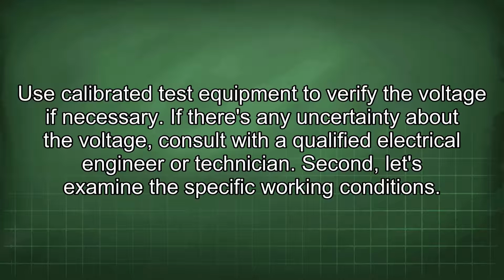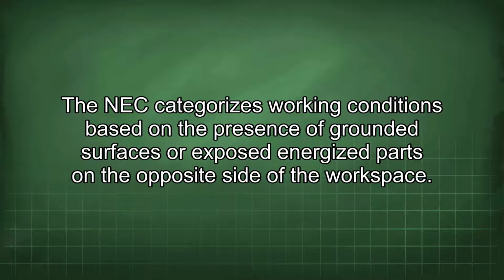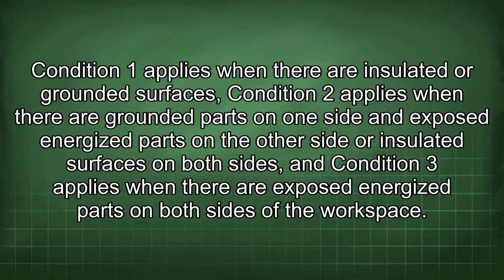Second, let's examine the specific working conditions. The NEC categorizes working conditions based on the presence of grounded surfaces or exposed energized parts on the opposite side of the workspace. Condition 1 applies when there are insulated or grounded surfaces. Condition 2 applies when there are grounded parts on one side and exposed energized parts on the other side or insulated surfaces on both sides. And Condition 3 applies when there are exposed energized parts on both sides of the workspace.